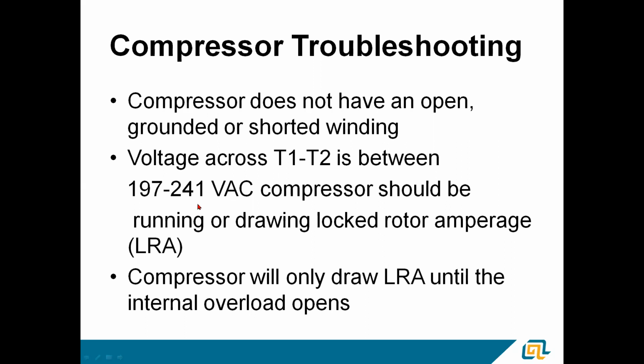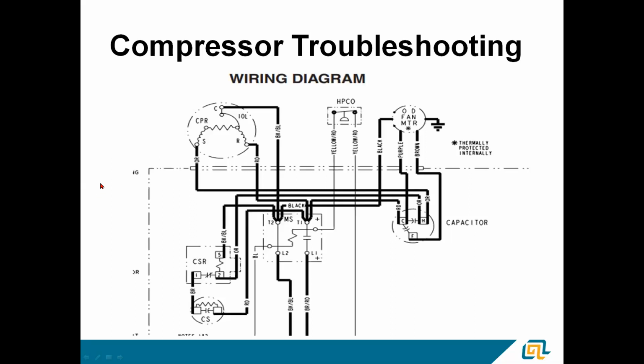And again, I'm going to go back a slide. I know, should never do that. If you notice, here's your internal overload inside the compressor. It breaks from R to common. And this little thing right here is actually a heater. It'll provide a little bit of heat on the underside of that internal overload to get it to open a little faster. And that's an amp draw thing. So a couple of safeties built into it. You might find that open. You'd find an open winding if you measured from R to common or start to common. You wouldn't get a connection.